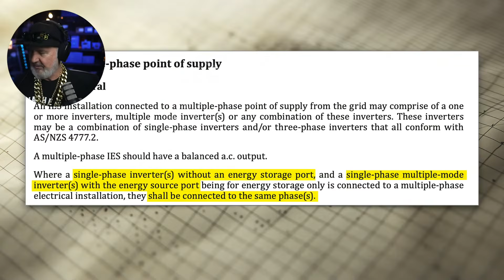Multi-phase point of supply: a three-phase installation with single-phase inverters without an energy storage port. What's that adding? Basically saying without a battery. A lot of the standard's wording is very generic - we don't use the words battery or energy storage. So if a single-phase inverter with no battery, and a single-phase multi-mode inverter with an energy storage port for storage only, are connected to a multi-phase installation, they shall be connected to the same phases. That's a wordy way of saying you can't put a solar inverter on phase A and a battery AC-coupled inverter on phase B - the storage inverter and solar inverter need to be on the same phase.